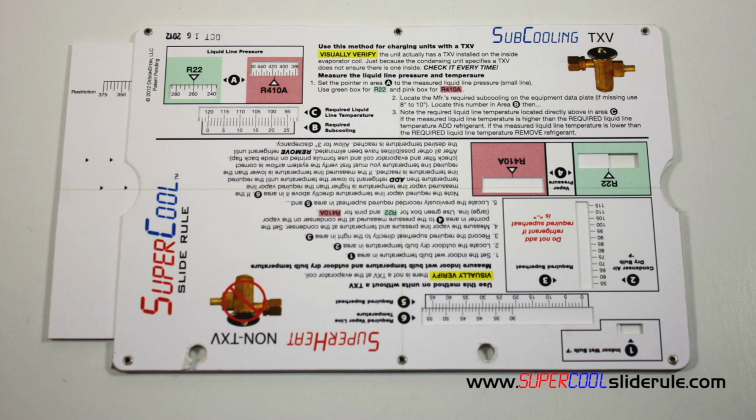In this tutorial, we will learn how to properly charge a unit with the subcooling method. If you have a super cool slide rule, get it out. We will be using it in this tutorial. We will be using the side labeled SubCooling TXV.